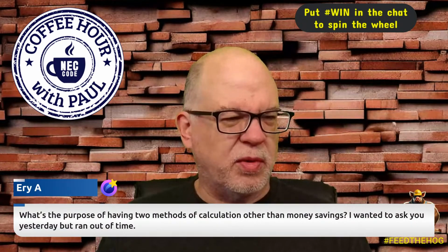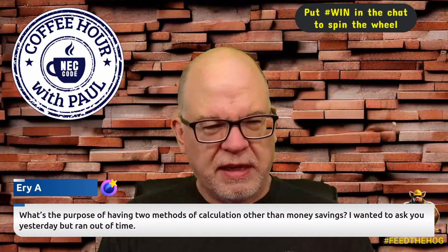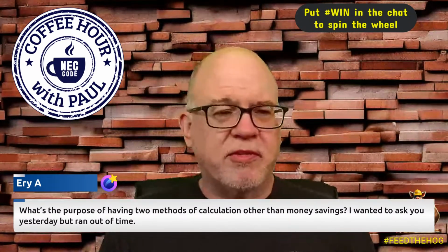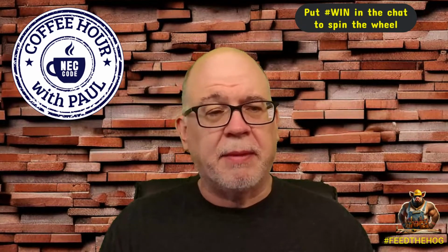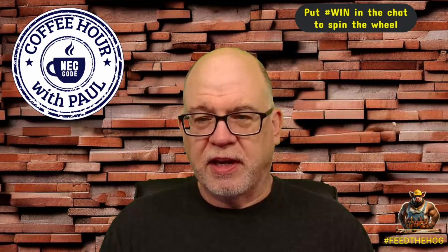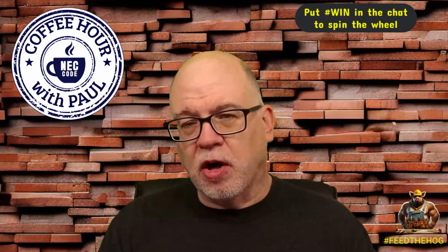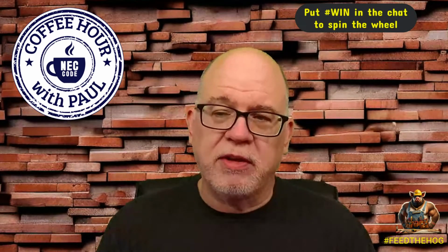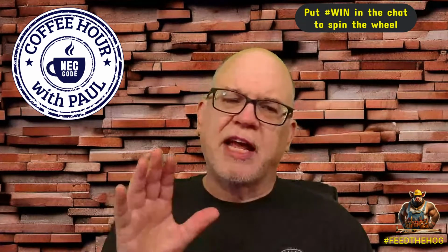Erie's got a question this morning. It says, what is the purpose of having two methods of calculation other than money savings? I wanted to ask you yesterday, but ran out of time. You mean with the traditional method versus the optional method? The optional method takes into account diversity, no different than the standard method. We need the standard method for sizing neutrals. There are some occasions where the standard method may yield a better result, but I wouldn't say the NEC cares about the money. It's not a money thing.